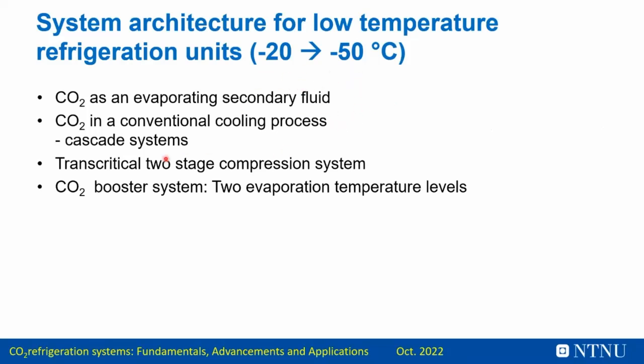I will show you CO2 as an evaporative secondary fluid, which is very often applied, or we can go into a system and look into a system with this cooling process, a cascade system, and then we look into a transcritical two-stage system. At the end we will see a booster system where we have two temperature levels, one for freezing and one for cooling.